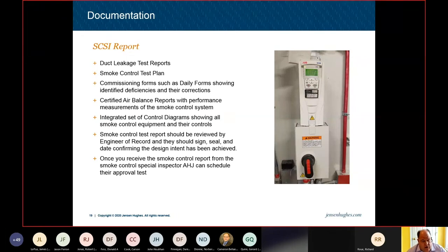And then the other pieces of equipment: the fire alarm has a lot more pieces to it, with field devices all over the place, so it's easier to add to that drawing where the air handling units are, where the variable frequency drives are. The photo right next to this, on the right, is a variable frequency drive, also known as a VFD, and that lets the certified air balancer tweak the fans on the smoke control systems. By changing the frequency, it changes how fast the fan spins and how much CFM it puts out. So it gives them another layer of control.